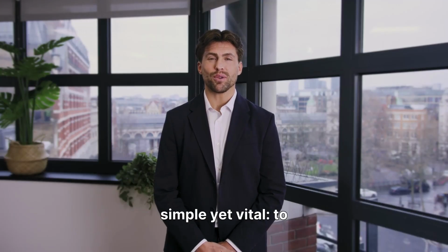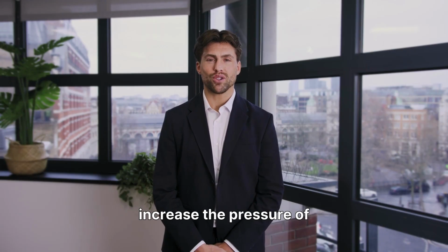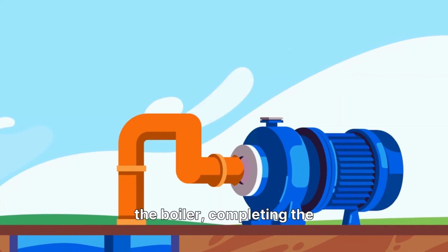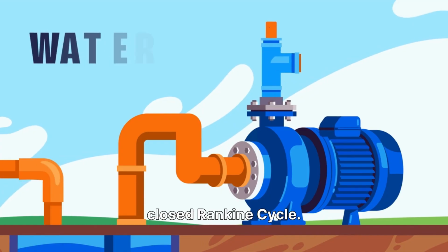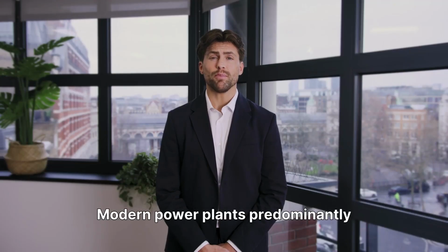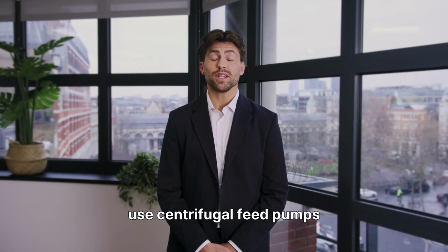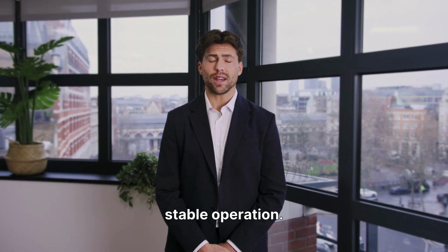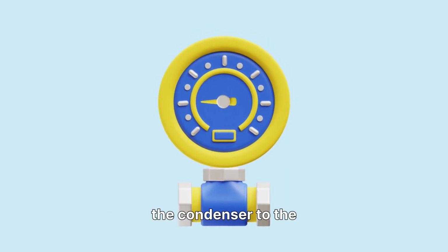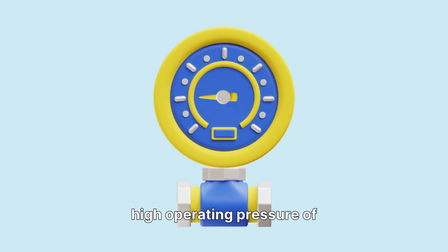Next comes the feed pump, whose job is simple yet vital: to increase the pressure of the condensate water. It then sends this high-pressure water back to the boiler, completing the closed Rankine cycle. Modern power plants predominantly use centrifugal feed pumps for their continuous and stable operation. The pressure is raised from near-vacuum conditions in the condenser to the high operating pressure of the boiler.